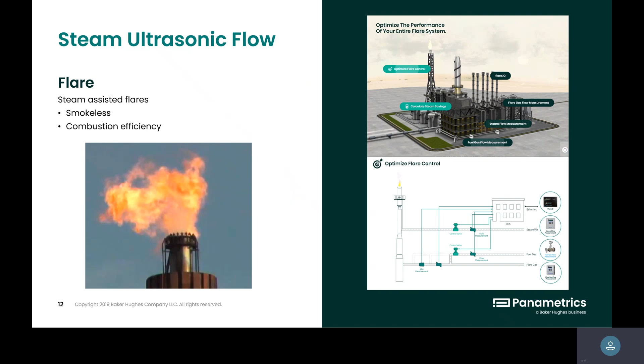And then moving on to petrochemical. This is a situation where this one customer wanted to save money. They really wanted to increase their measurement range with higher turndown, but at the end of the day, the driving factor was no maintenance. They were sick of the maintenance associated with it, having to keep calibrating, keep trimming, go into the field, and change it. They wanted something more reliable that they could just install and move forward. So they took a look at ultrasonics. They had one installed at a sister plant. They compared it against another, I think a differential pressure measurement, and you can see the trending was almost dead on. It absolutely performed. They were so happy.